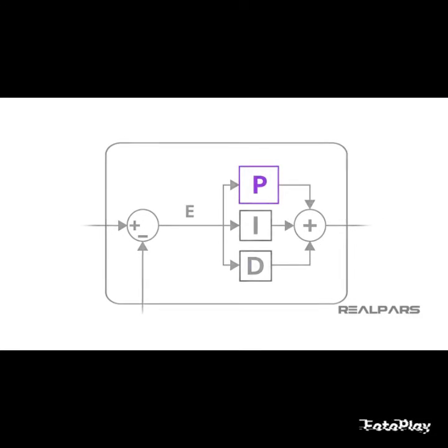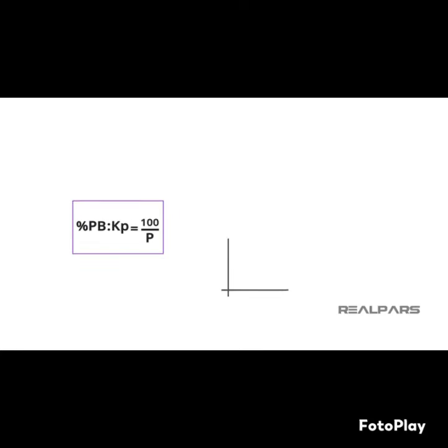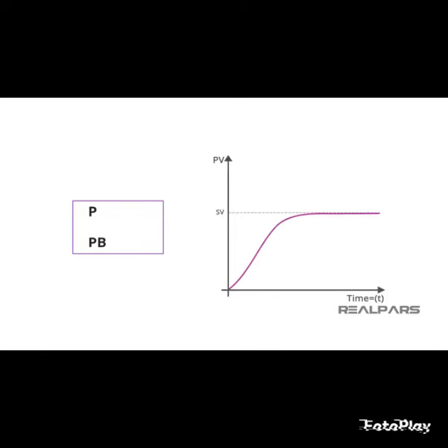The proportional term, often called P constant, can be referred to as proportional gain, or just gain, which is not a unit but instead a ratio. This parameter can also be called proportional band and measured in the unit of percent. This parameter can be called Kp, gain, or others. This is the parameter that determines how fast the system responds. The name by which it is referred varies with the manufacturer.